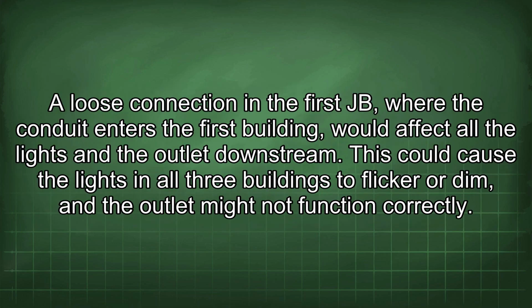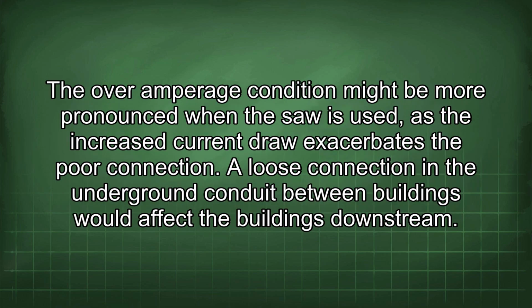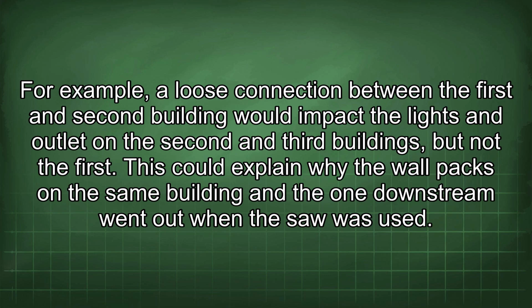A loose connection in the first JB, where the conduit enters the first building, would affect all the lights and the outlet downstream. This could cause the lights in all 3 buildings to flicker or dim, and the outlet might not function correctly. The overamperage condition might be more pronounced when the saw is used, as the increased current draw exacerbates the poor connection. A loose connection in the underground conduit between buildings would affect the buildings downstream. For example, a loose connection between the first and second building would impact the lights and outlets in the second and third buildings, but not the first.